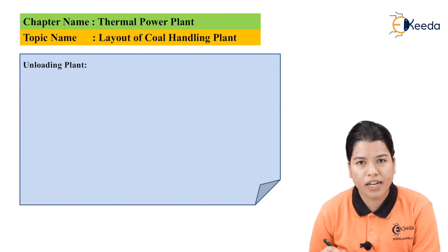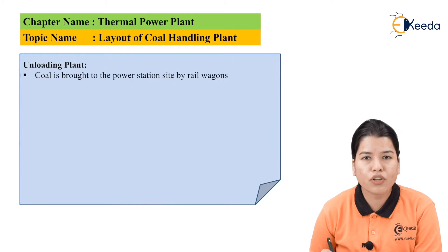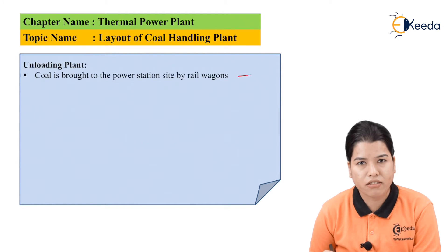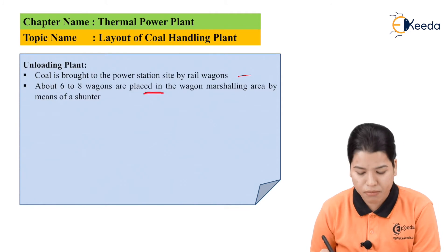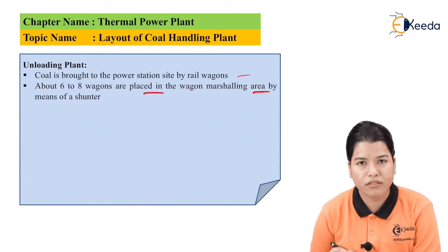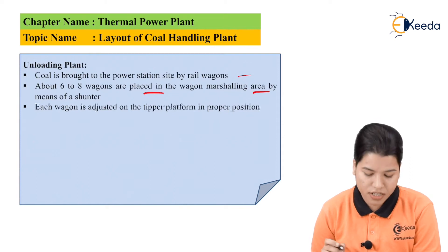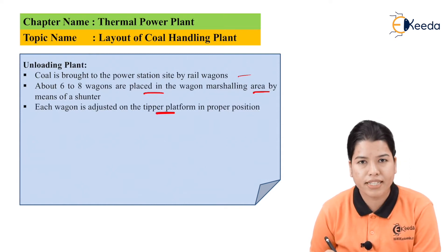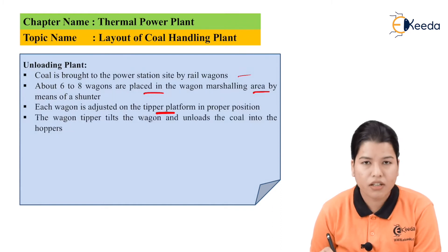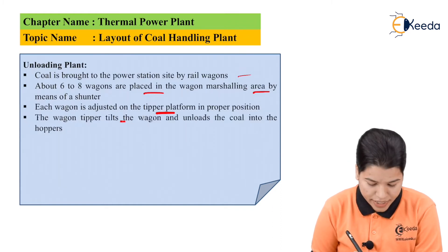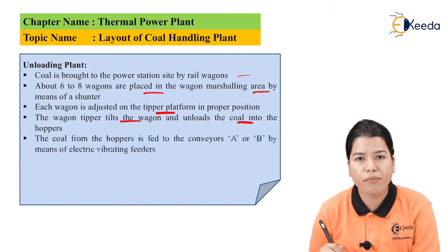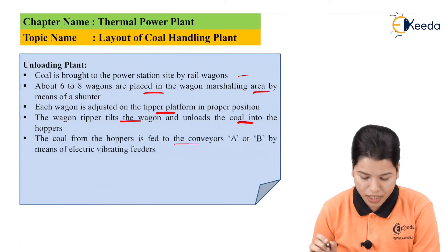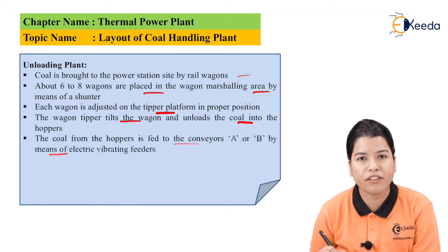First, we will study about the unloading plant. The coal is brought to the power station from the particular site by rail or by train. About 6 to 8 wagons are placed in the wagon marshalling area by means of a shunter. Each wagon is adjusted on the tipper platform in the proper position. The wagon tipper tilts the wagon and unloads the coal into the hopper. The coal from the hopper is fed to conveyors A and B by means of electric vibrating feeders.